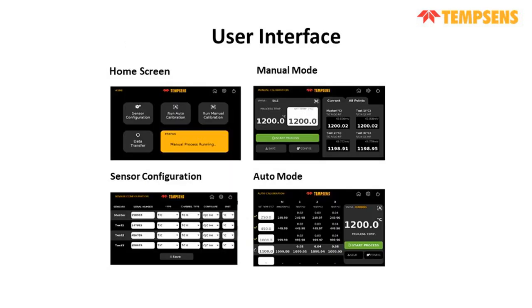This is the home screen of the optical model. In the sensor configuration, we can configure the sensors. In the third screen, you can see the serial number, type, channel type, configuration, and then the unit in degree centigrade or degree Fahrenheit, whatever we want. Then we have run auto calibration or run manual calibration. For the auto calibration, we have this auto calibration screen in which 5 temperatures will be set at a time. For the manual calibration, one temperature will be done at a time. In the auto mode, you can see master, test 1, test 2, test 3 are given. Once it is completed, it is under processing, and then we can click on save to save the file, and then the data will be saved.